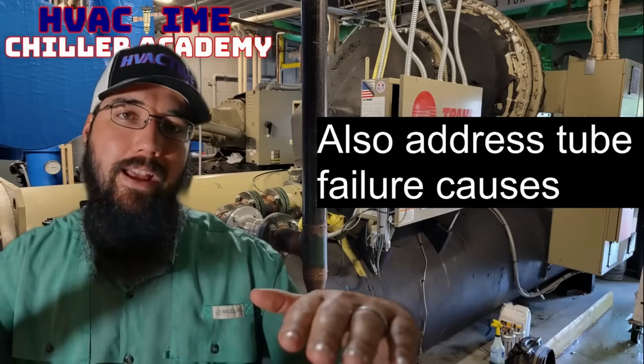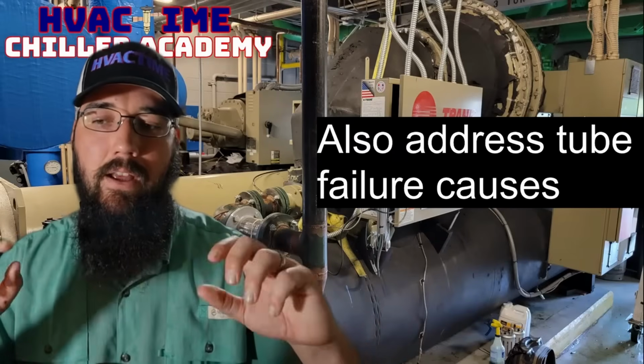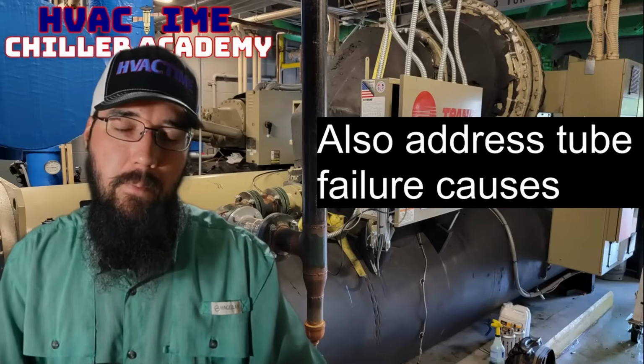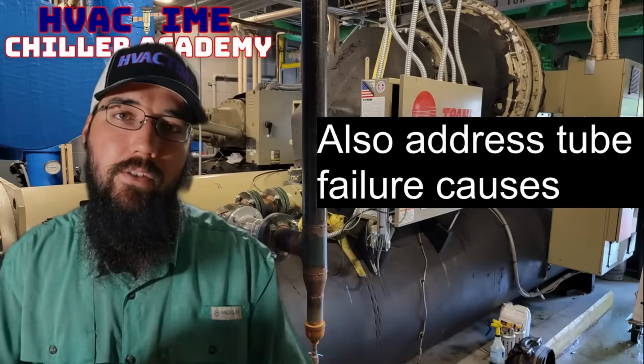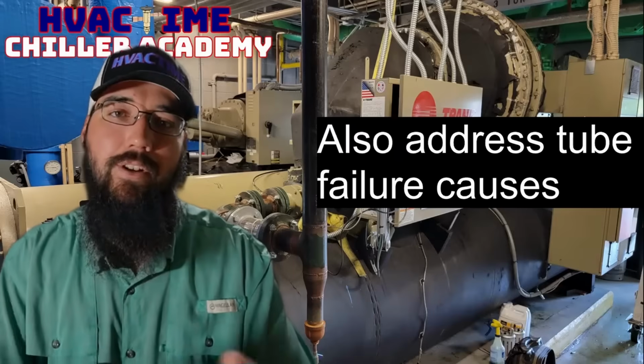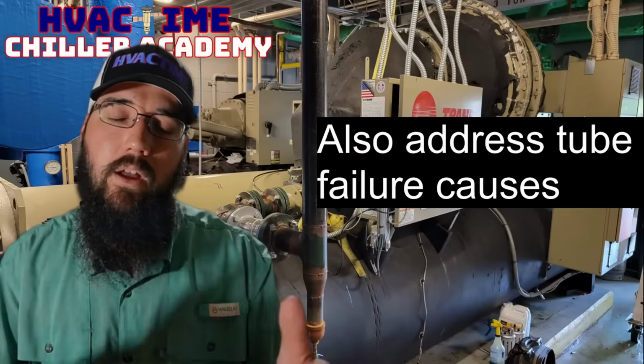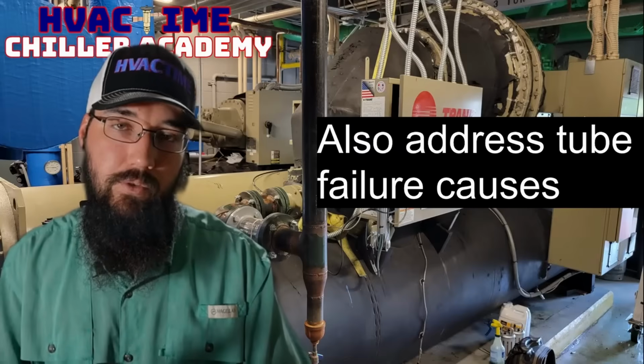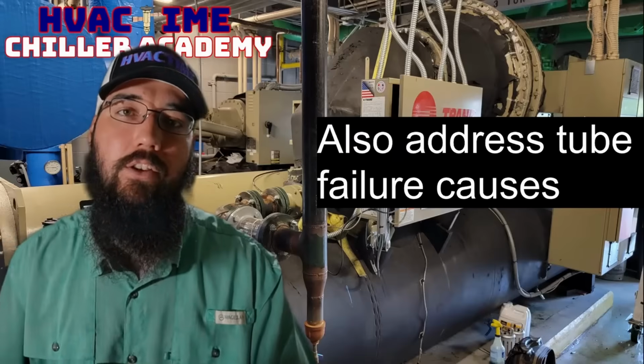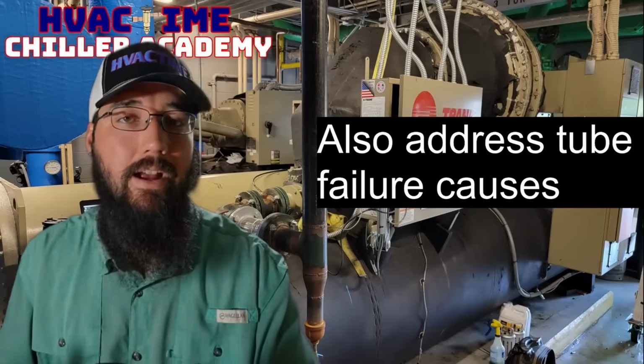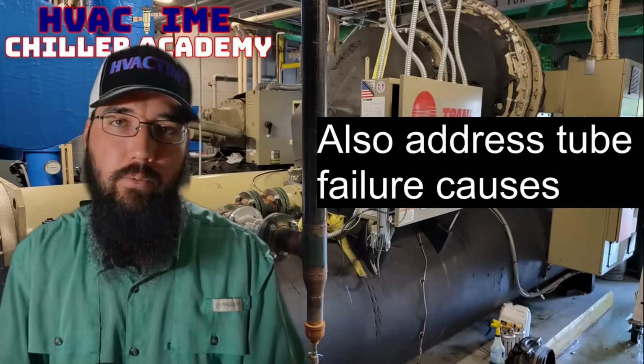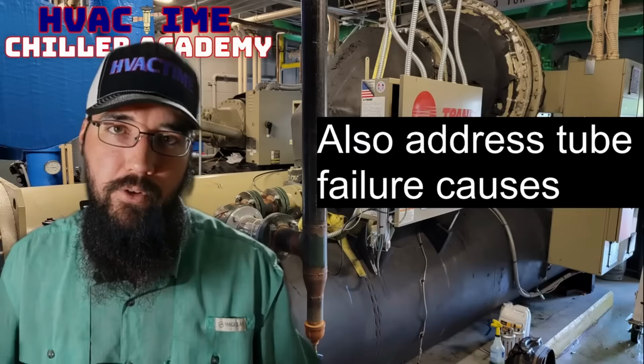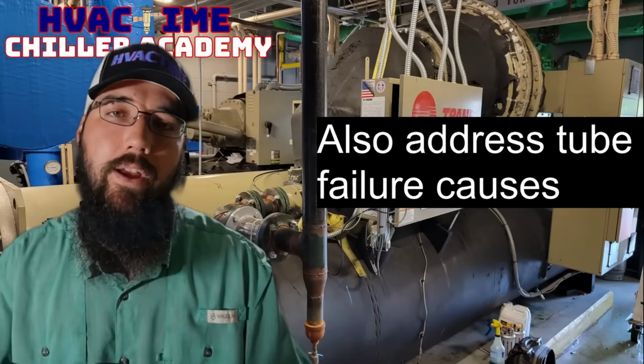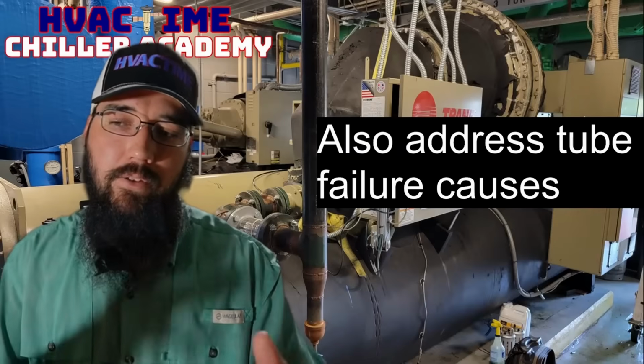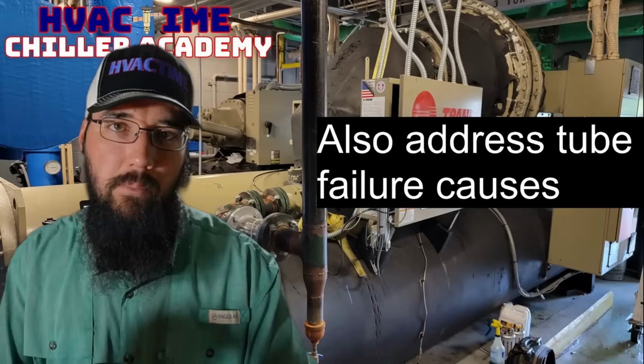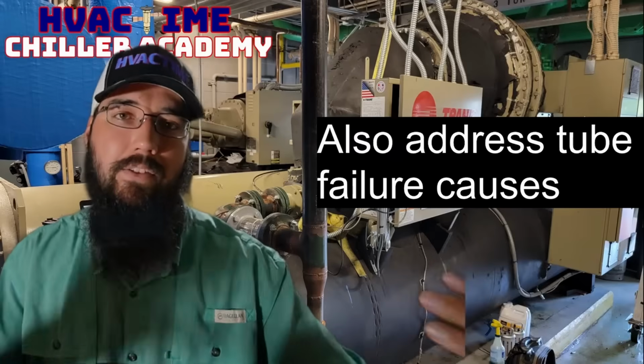It is very important that we maintain proper liquid level in the condenser for a YK, because if the refrigerant level drops too low, it creates a lot of currents, or specifically eddy currents, inside of the subcooler housing. Those eddy currents will allow extra turbulence to rub on the tubes. And that extra rubbing will eventually lead to a hole being rubbed in a tube because of the rack. And then that leads, obviously, to the hole in the tube, you had a failure, right? And then your water and refrigerant start to mix. That's an example of a situation that can happen where, if not managed correctly, the tube can rub and get a hole rubbed in it from the rack assembly itself.